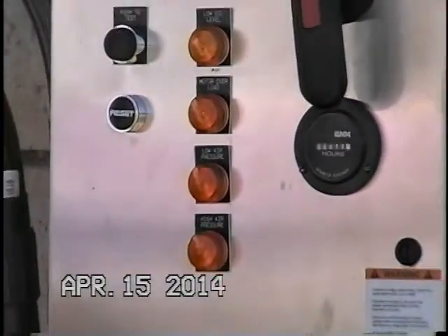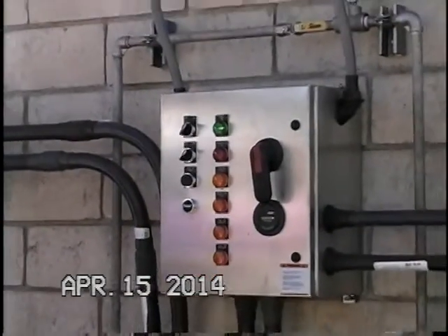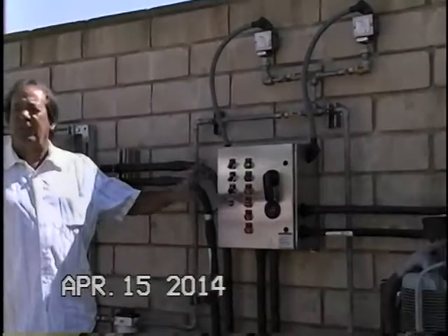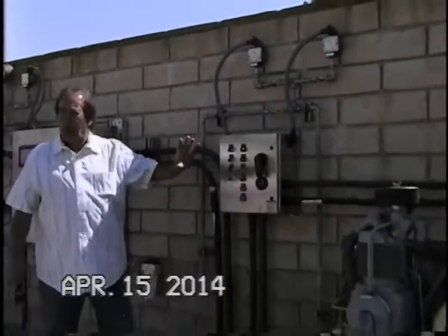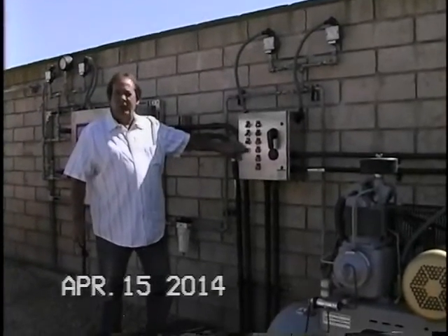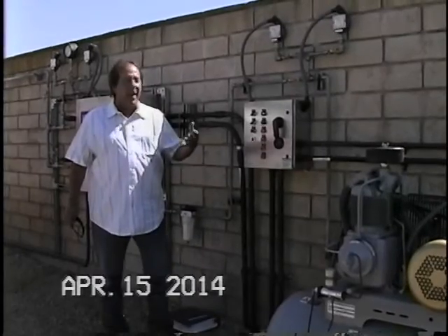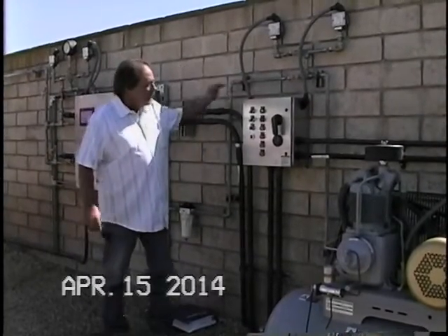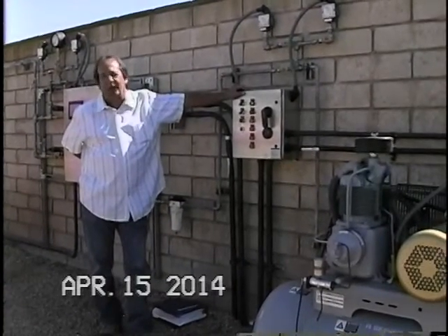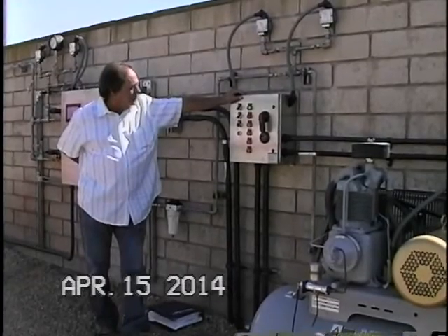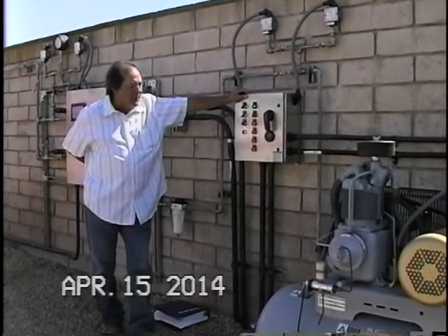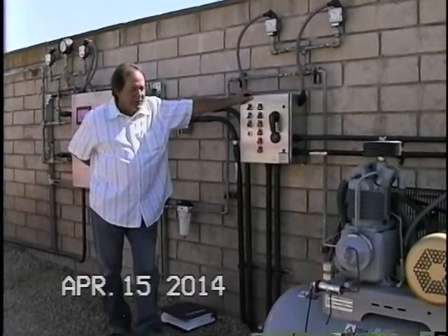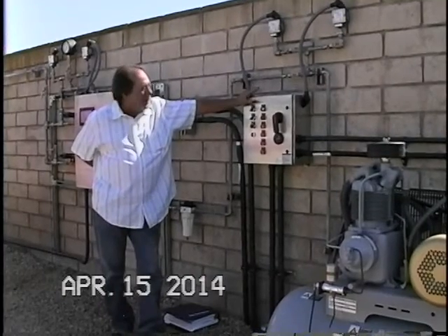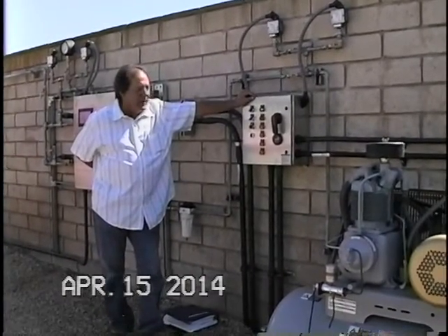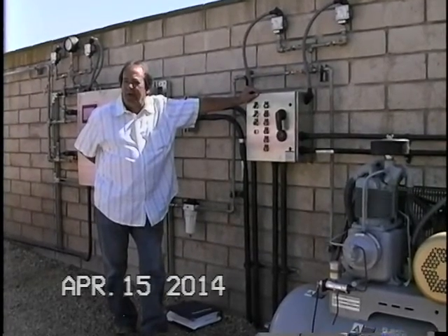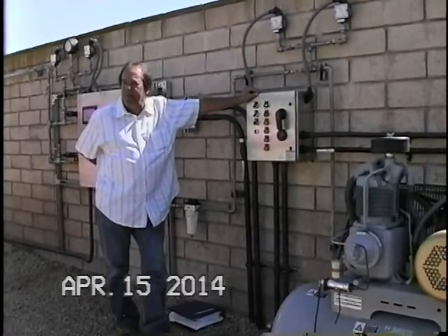Those are all the alarms used to monitor the compressed air system, and they are all latched alarms. So in every case, if you have an alarm, you're going to have to come out here and acknowledge it and reset it, but it's only going to reset if it's back into a normal condition. So if you're on the low oil level, likelihood is you better add some oil, otherwise she's not going to start. Other than that, that's pretty basic. It's a standard system. There are no other real special features other than our alarms and changing the oil. Those are your main operation and maintenance items that you really need to take care of.